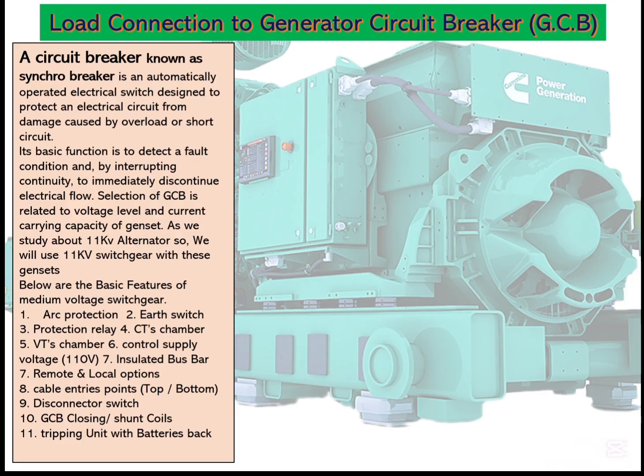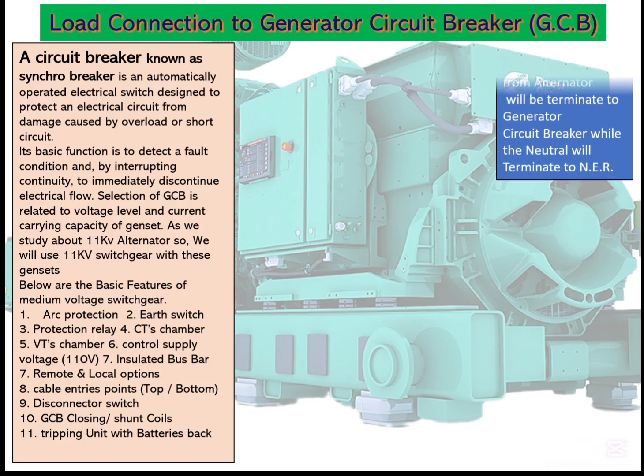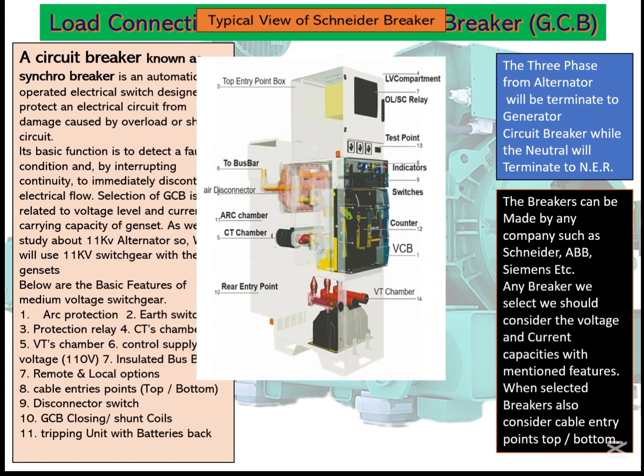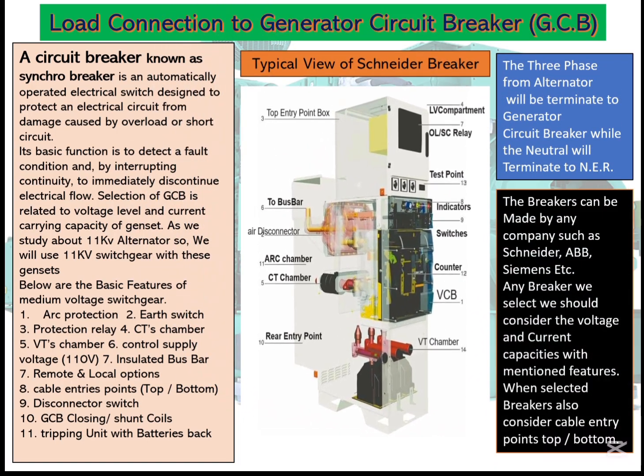A circuit breaker, known as a synchro breaker, is an automatically operated electrical switch designed to protect an electrical circuit from damage, either overload or short circuit. So it has safety, it has the protection of relays, a charging mechanism, and different relays: closing, opening, and shunt UVT relays. Then it has a disconnector. So let's look at a typical view of the breaker. This is a typical view of a Schneider Evolis breaker. So all this we discussed. We can see them here, their location.